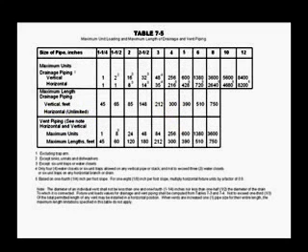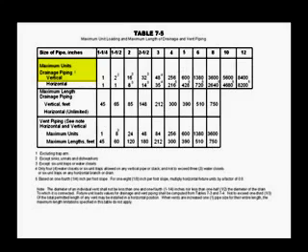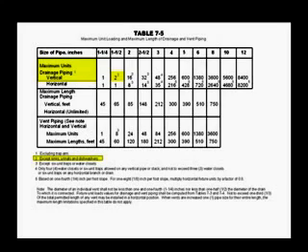Maximum Units Vertical. Note that 1-1/4 inch pipe will handle only one fixture unit, so go to the next higher pipe size and note the small number 2 for footnote number 2 at the bottom of the table. It reads, except sinks, urinals, and dishwashers. The lavatory is not included in this exception, so the 1-1/2 inch drain will carry the fixture unit load.